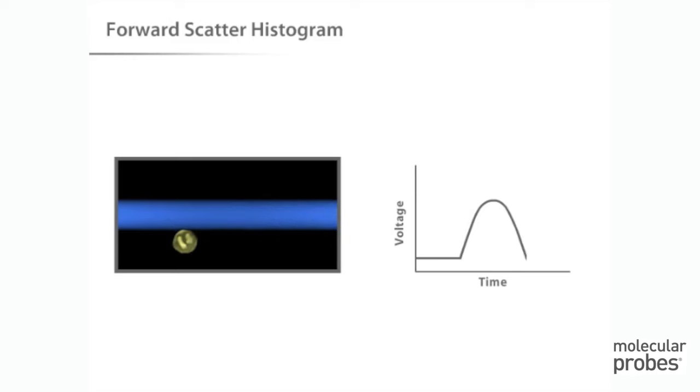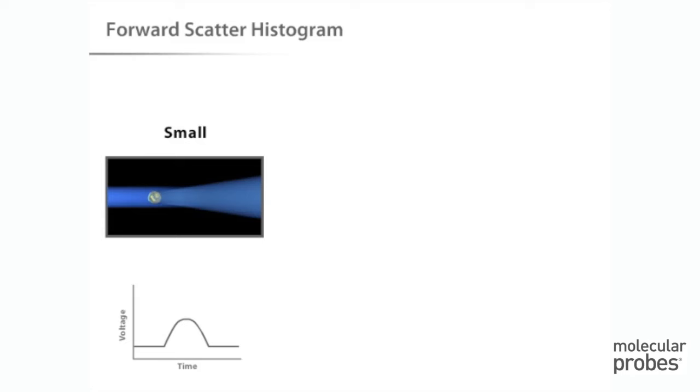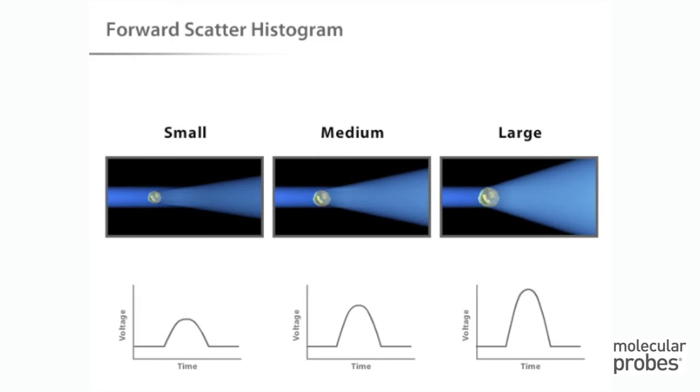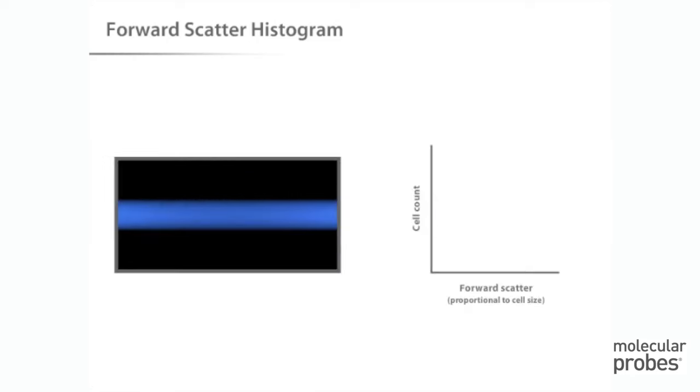The scattered light received by the detector is translated into a voltage pulse. Because small cells produce a small amount of forward scatter and large cells produce a large amount of forward scatter, the magnitude of the voltage pulse recorded for each cell is proportional to the cell size. If we plot a histogram of these data, smaller cells appear toward the left, and larger cells appear toward the right.